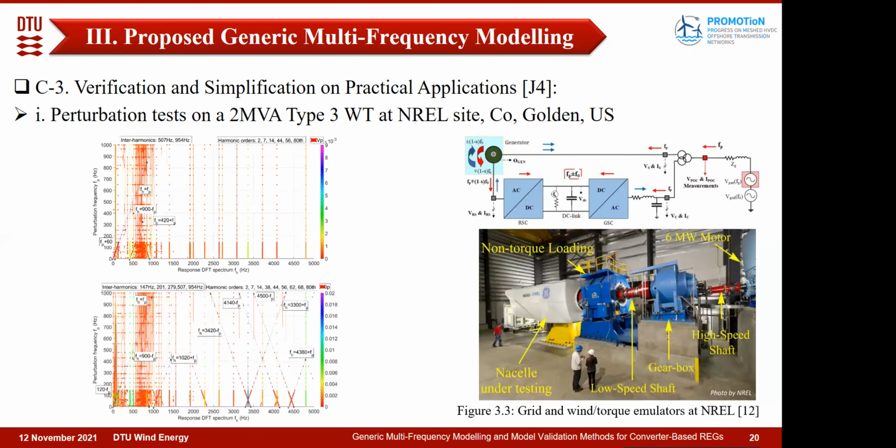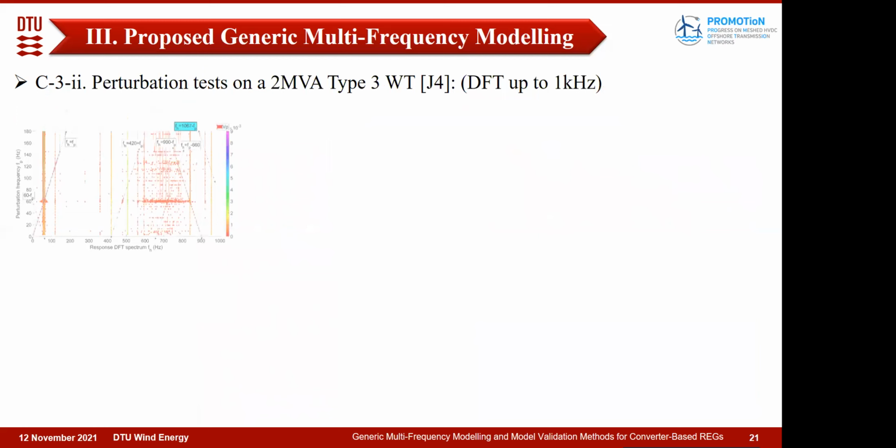So first we look at the general view. In these figures from positive sequence voltage and current up to 5 kilohertz, we can see what is happening in the whole range. Here it is not much observable for the dependent couplings. But still, we can see, for example, high frequency couplings, which are related to the switching frequency of the converter. So to understand this better, in the next slide, we will zoom in on that range.